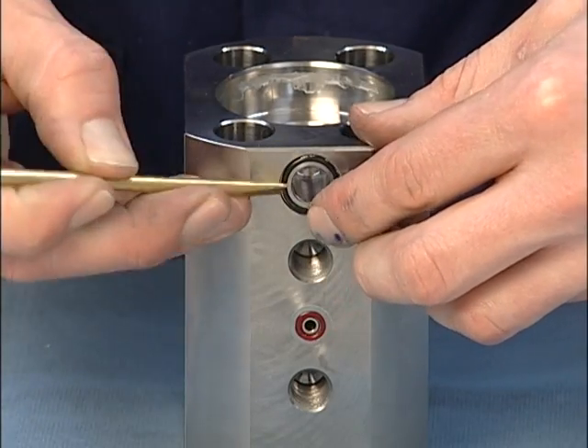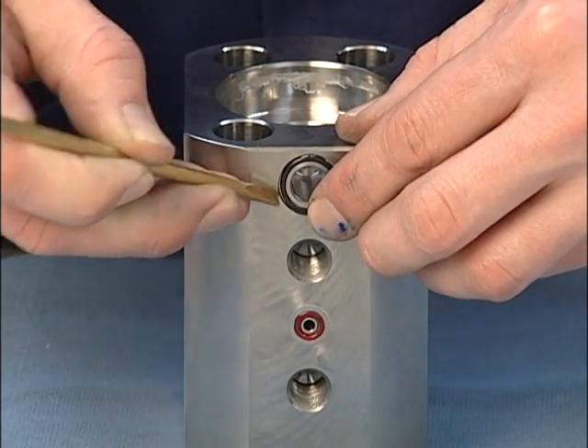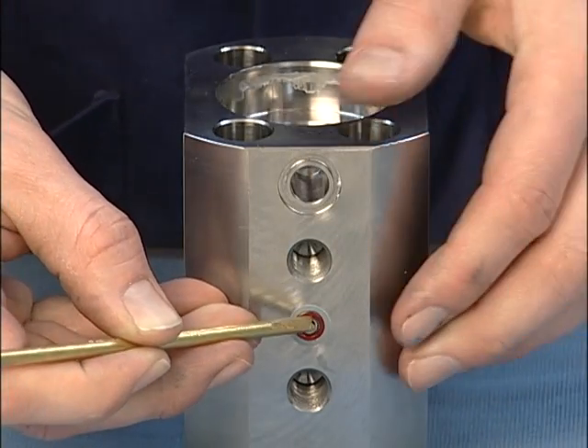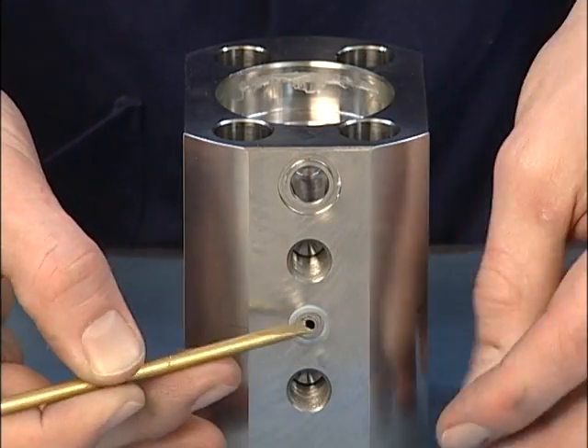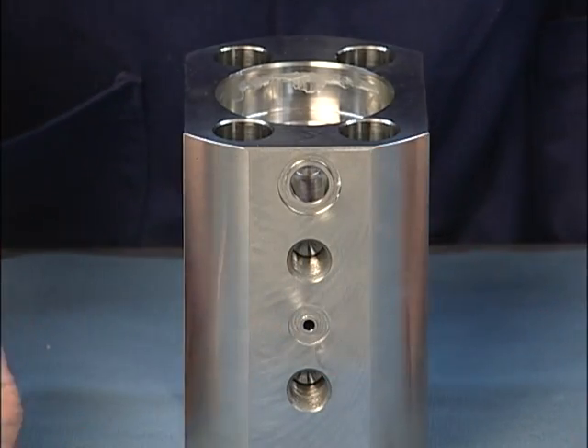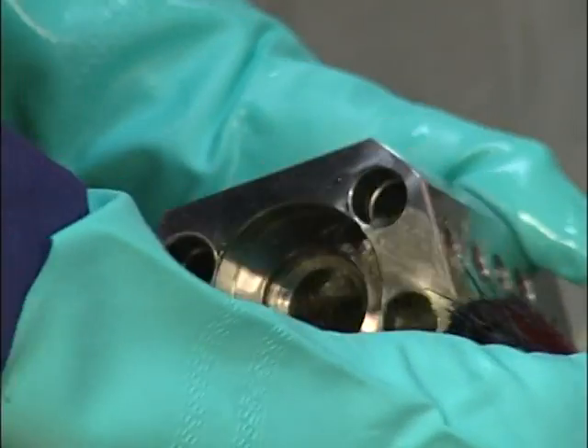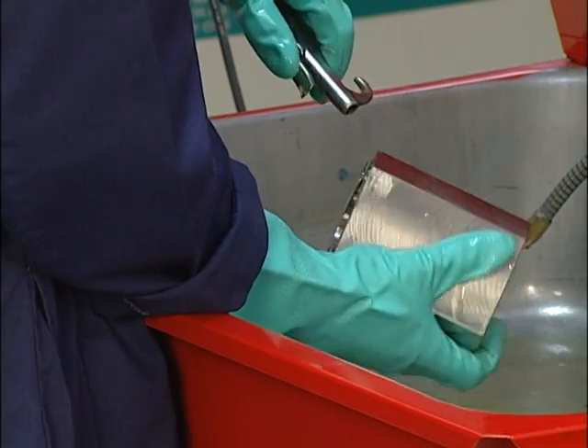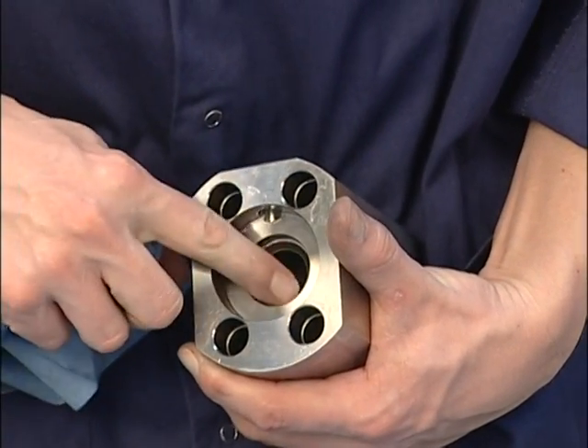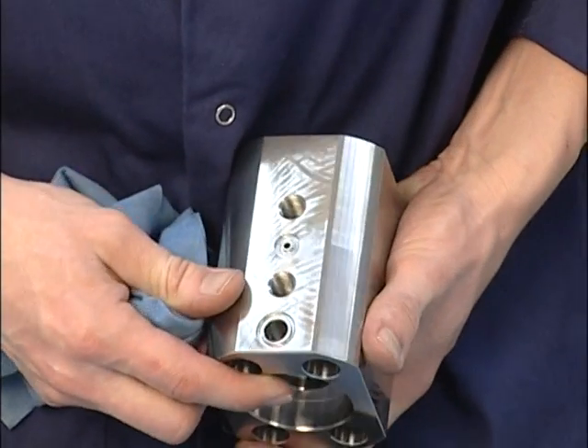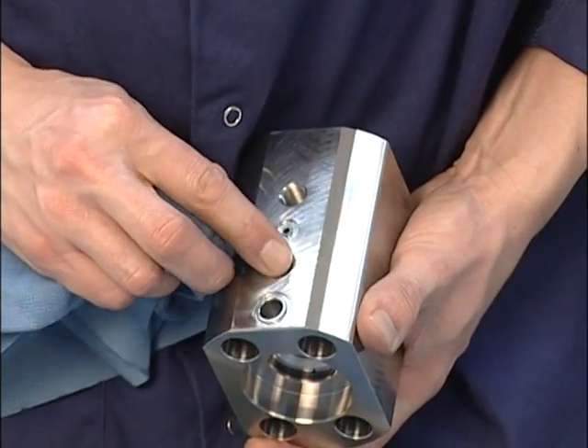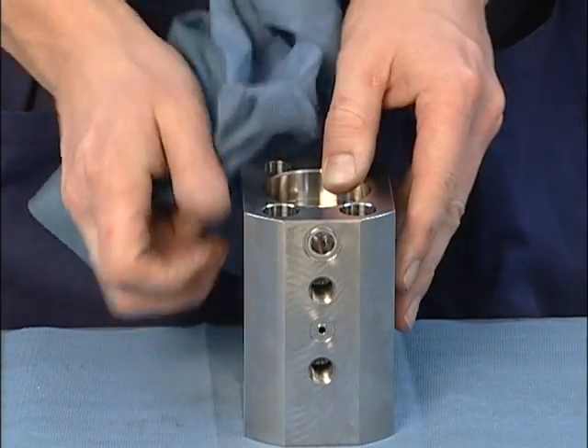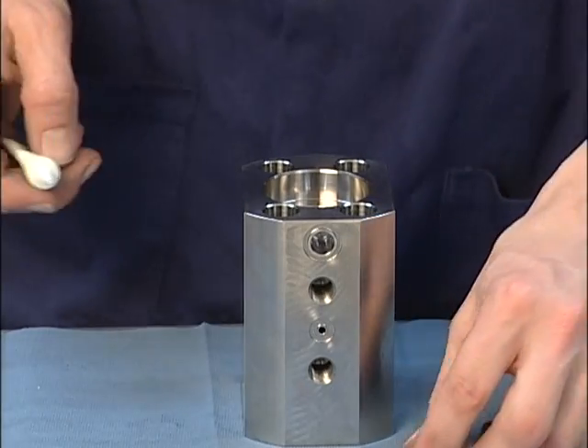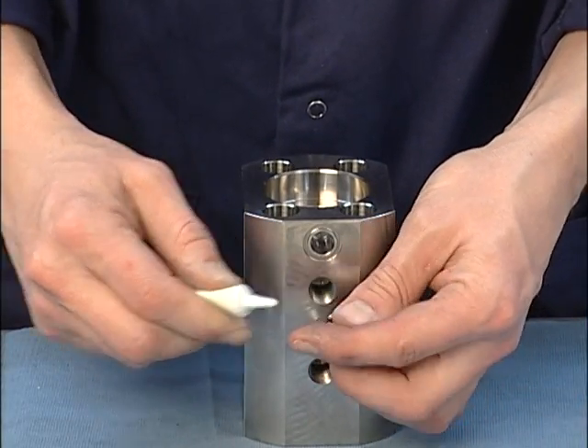Remove the two O-rings and high-pressure seal from the end cap and clean the end cap using solvent and compressed air. Inspect the end cap for cracks, erosion, and pitting. Replace if needed. Inspect the O-rings and high-pressure seal for damage. Replace them if needed. Lubricate the O-rings and high-pressure seal with a small amount of white food-grade O-ring lubricant and install them into the grooves in the end cap.